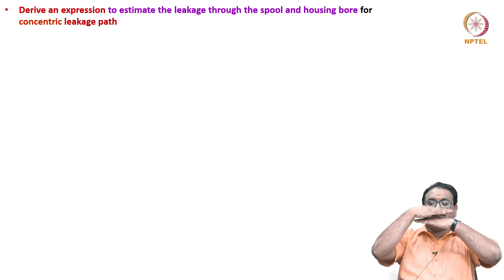You will see here, friends, the middle one is a spool mounted concentrically, meaning the axis of the bore and the spool axis coincide with each other. You will see this in the side view also. There is always a clearance because the spool is moving inside the bore. It requires a small clearance. If clearance increases, leakage increases. Please understand, friends, the clearance is very critical in the case of spool valves. If clearance increases, leakage flow increases. If clearance decreases, manufacturing cost increases. Take care of this also.